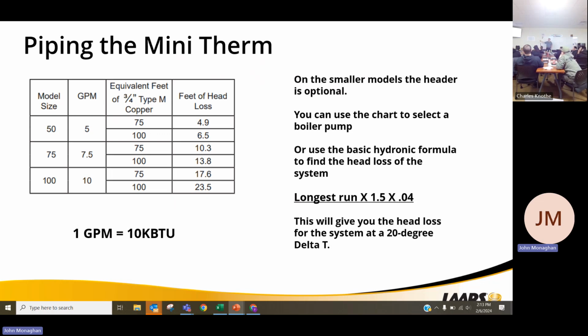That formula down there at the bottom is going to basically figure out your pump head loss. We usually don't know what our gallons per minute are. Gallons per minute are going to be the BTUs that we're looking to deliver. We're trying to figure out our BTU ranges. If you're doing copper fin baseboard, quick rule of thumb, every linear foot of element is 600 BTUs at 180 degrees.